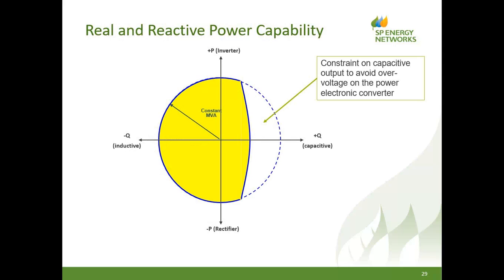This is one of the key functionalities of DC technology or VSC technology. On the y-axis, I've shown power. On the x-axis, I've shown reactive power. Essentially, this technology can provide a constant MVA capability. We can import or export power as we will. We can import or export reactive power as we will. We do have a constraint.